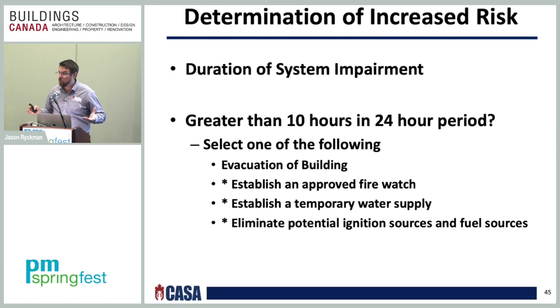It's basically management 101. Also, the duration of the system impairment. So the standard talks about the requirements. Also, the fire code does as well. But when talking about the standard, anything greater than 10 hours in a 24-hour period, you have to select one of the following options. So you either evacuate your building, you establish an approved fire watch by the authority having jurisdiction, you establish a temporary water supply, or you eliminate potential ignition sources and fuel sources. Those are your options.